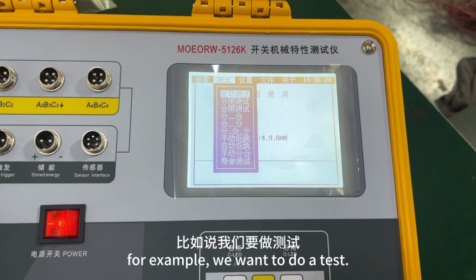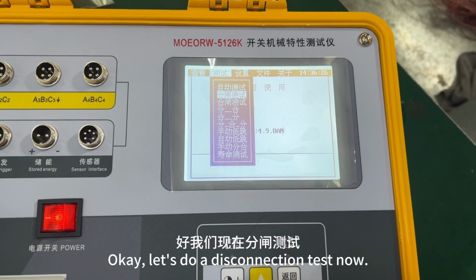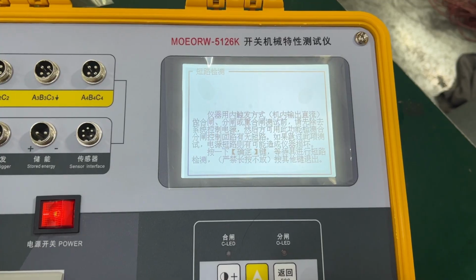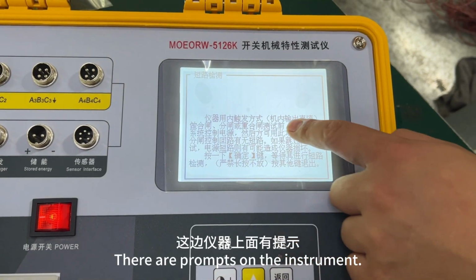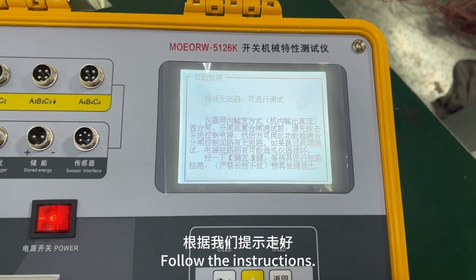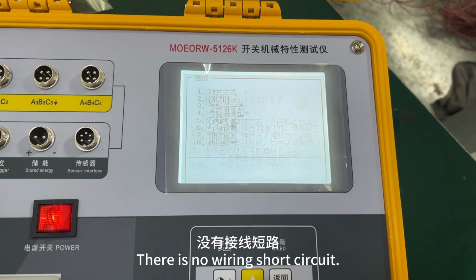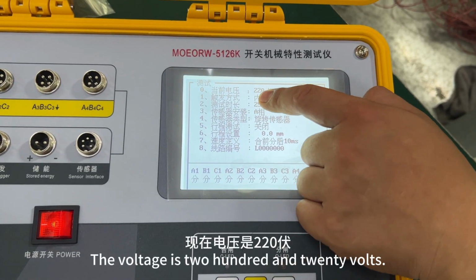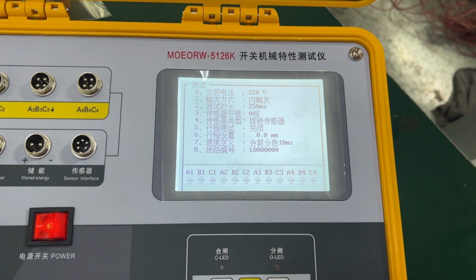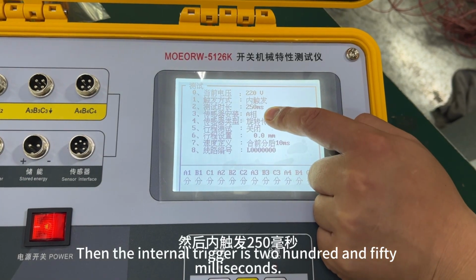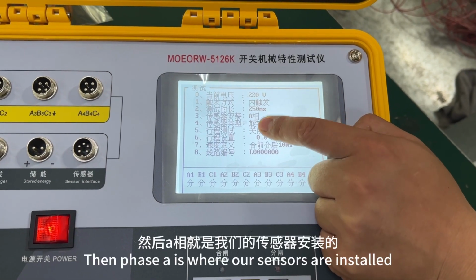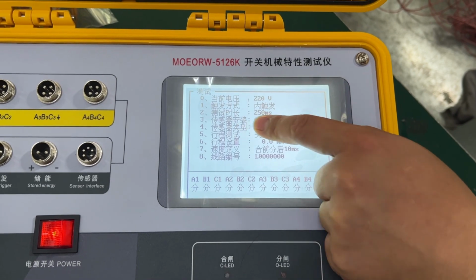For example, we want to do a test. Okay, let's do a disconnection test now. There are prompts on the instrument. Follow the instructions. There is no wiring short circuit. The voltage is 220 volts. Then the internal trigger is 250 milliseconds. Then phase A is where our sensors are installed.